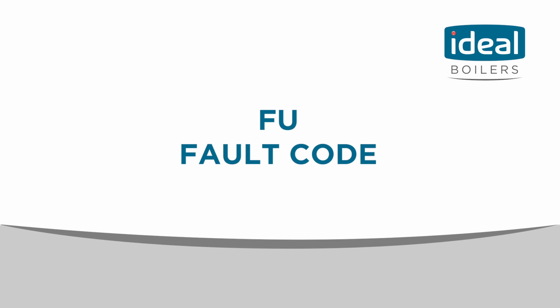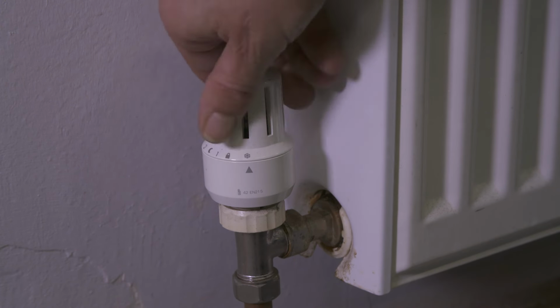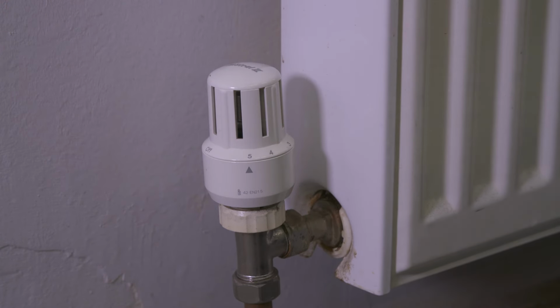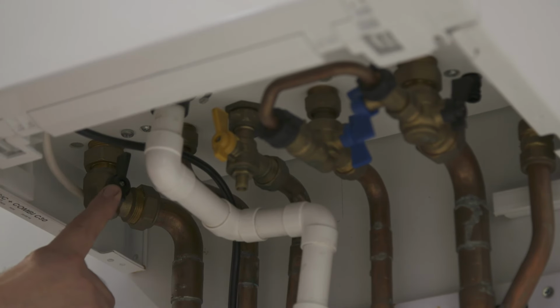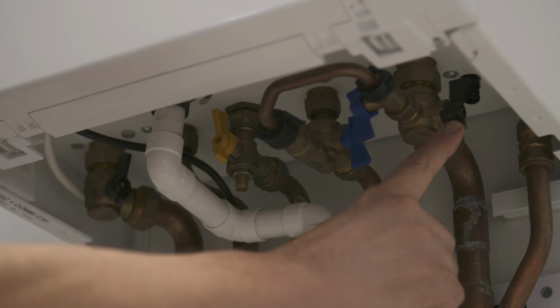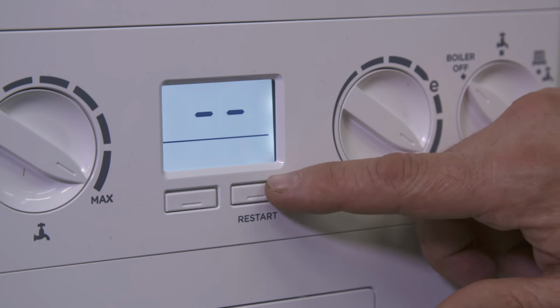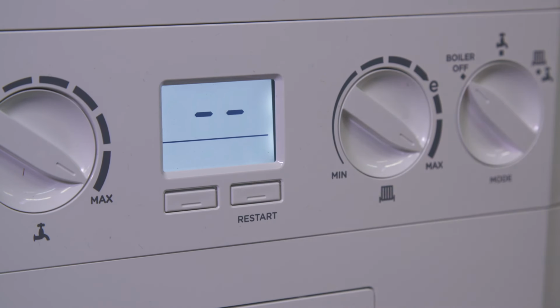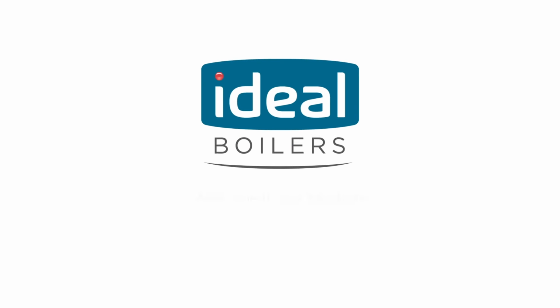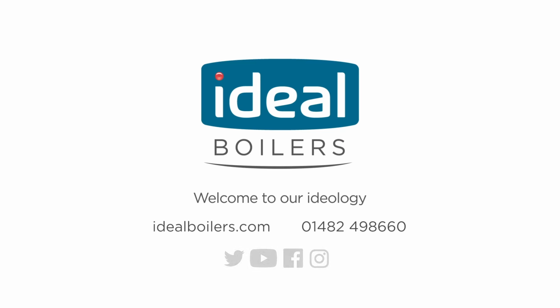If you encounter an FU fault code, it means that we have a big temperature differential across the flow and return. Ensure all the radiator valves are in the open position and the isolation valves underneath the boiler are also in the open position. Try a restart. If the fault persists, contact Ideal Boilers. For any other fault codes, please contact Ideal Boilers.